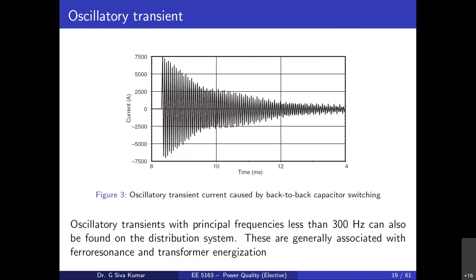Oscillatory transients are generally associated with ferroresonance, and transformer energization also will be called an oscillatory transient. But this phenomenon of ferroresonance is much similar to a resonance phenomenon, only it is based upon the variation in the inductance. Basically, due to the variation of the inductance only, it is going to occur. We'll see this kind of ferroresonance. The concept of ferroresonance is also in the harmonic sources.